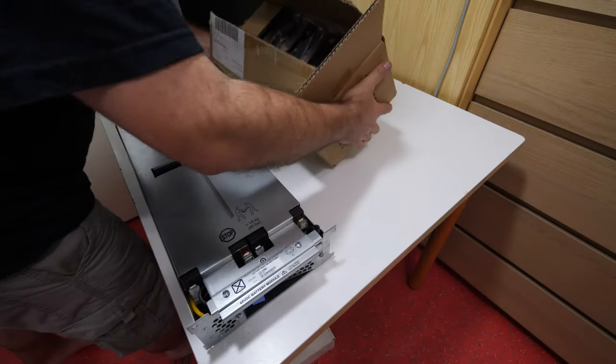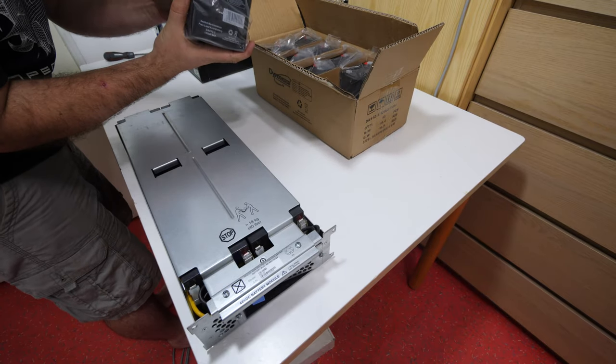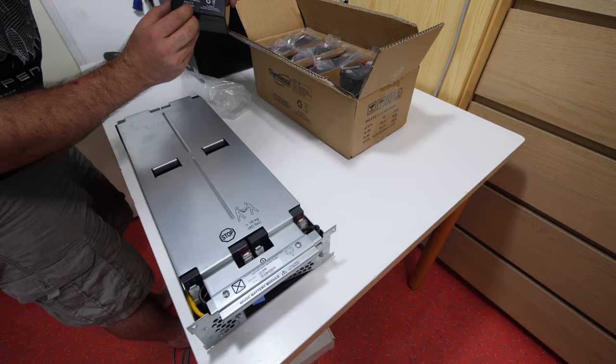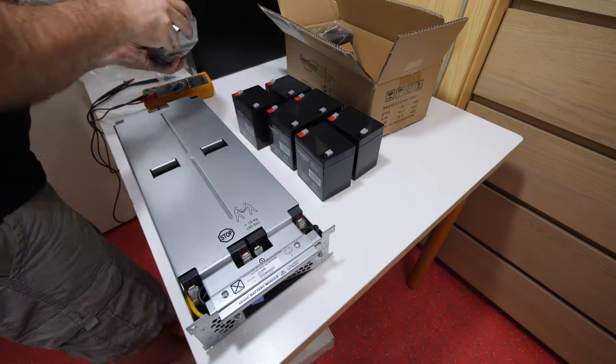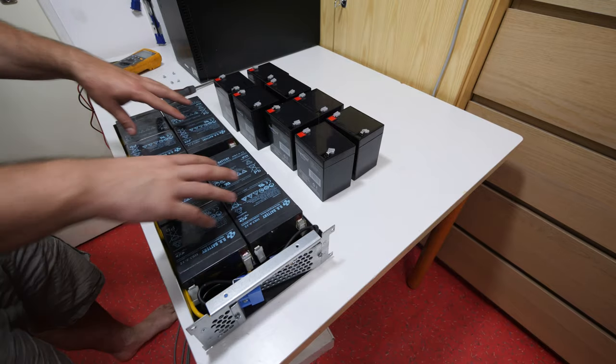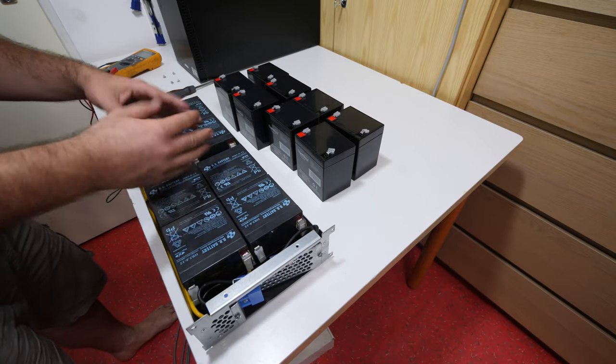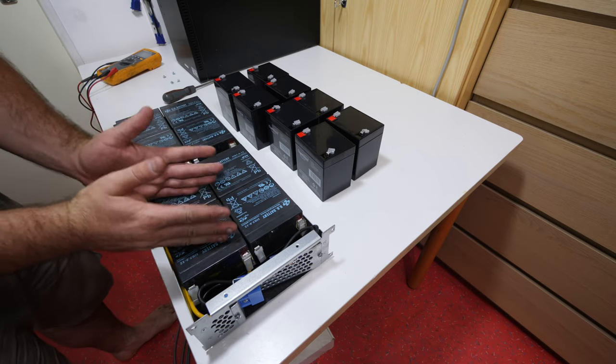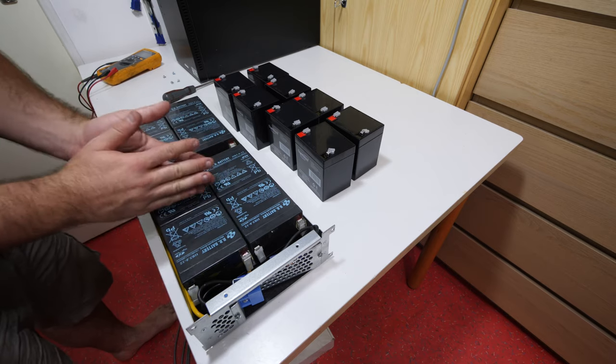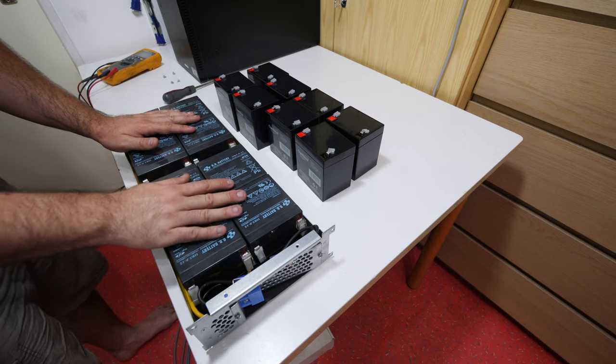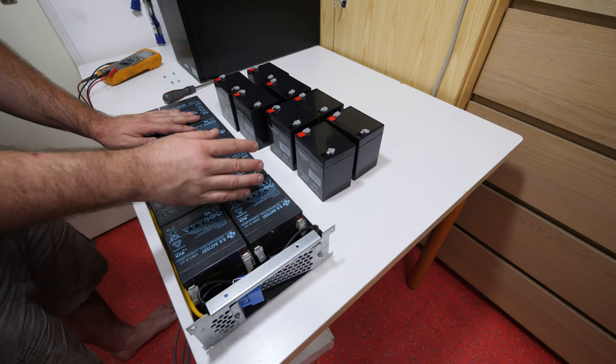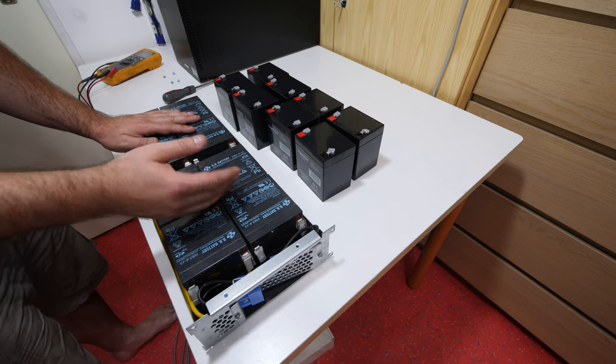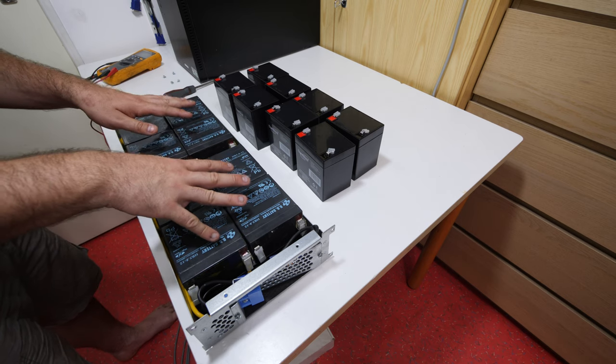I bought replacement batteries. In this unit we have 8 batteries, and they are 12 volt 5 ampere. Always check for white stuff around it, because then they are leaking. That can damage metal and power lines and everything. If you are replacing a leaking battery and you need to clean under it, just clean it with water.